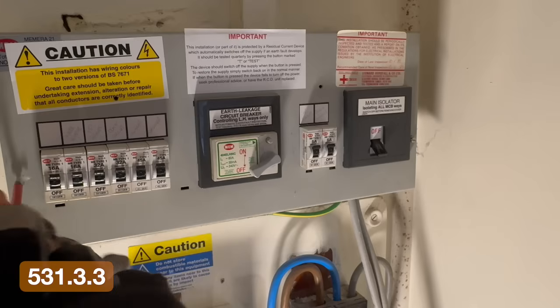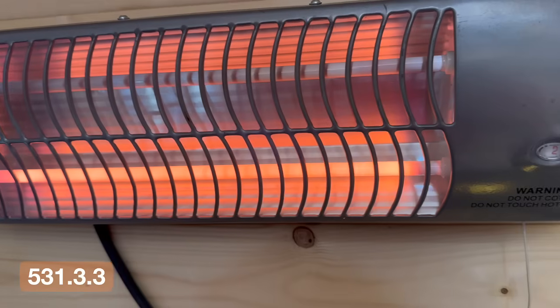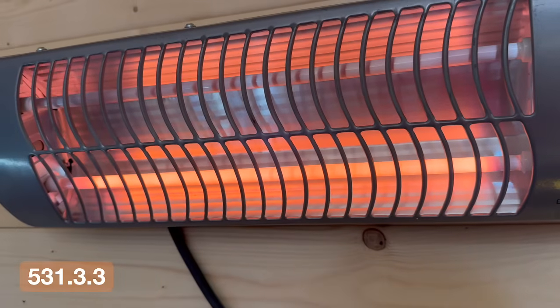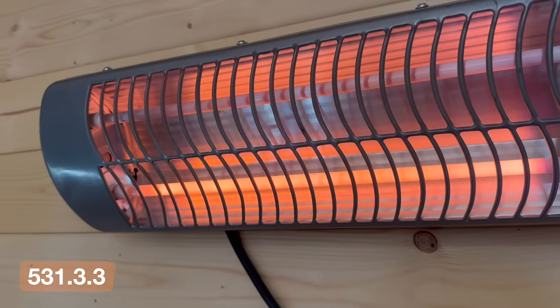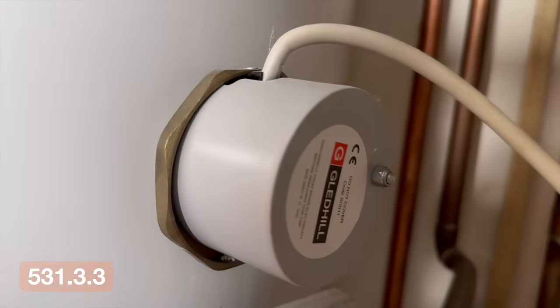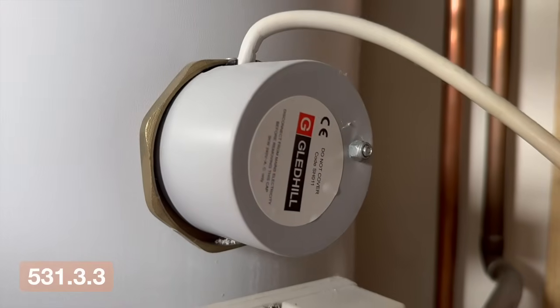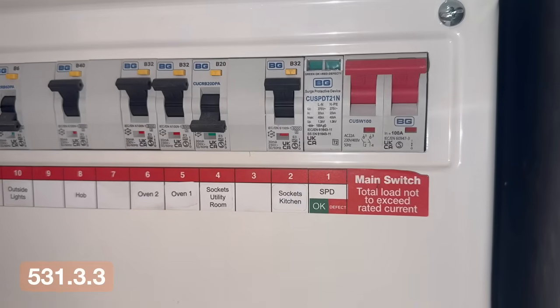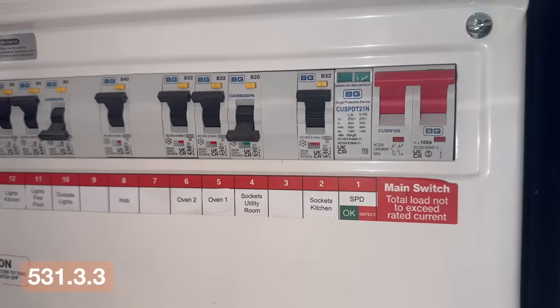And the biggest shift is around type AC RCDs. These are now heavily restricted. They can only be used where it's known that the load current contains no DC components. In reality, that limits them to very simple circuits, things like basic resistive loads where the waveform is predictable. Everything else now pushes you towards type A as a minimum, and in some cases type F or type B, depending on the equipment being installed.